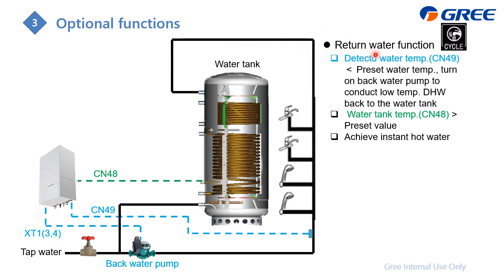First is the return water function, which is the instant hot water on the controller. When you activate this function, it will display this icon. And here is how it works. We also need to install the water temperature sensor on CN49, and basically put it here, near the user water. If we detect this water temperature is less than your setting, and also during your preset time, we can turn on this backwater pump to circulate the water back from here to the water tank. And the user can get the hot water from here immediately, or instantly.